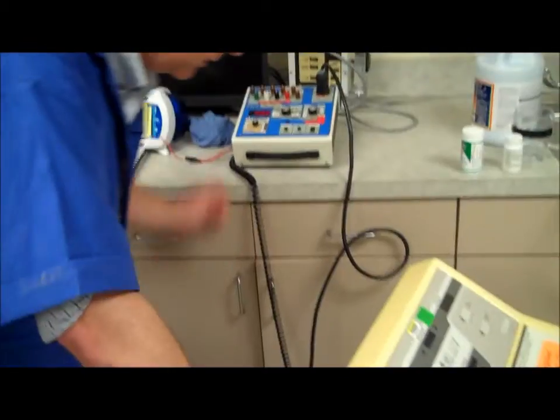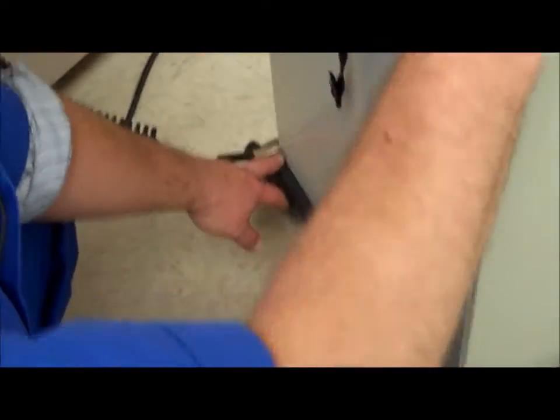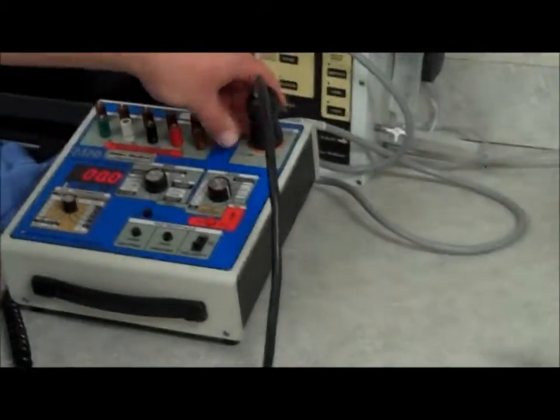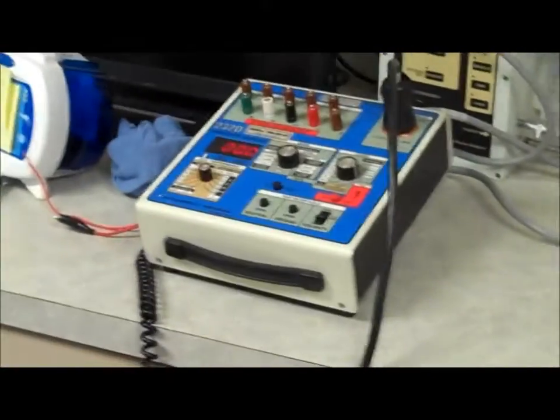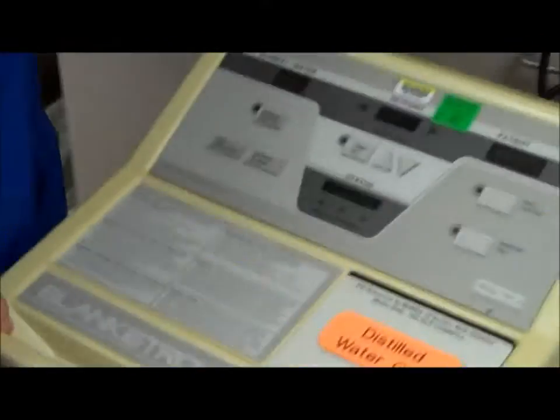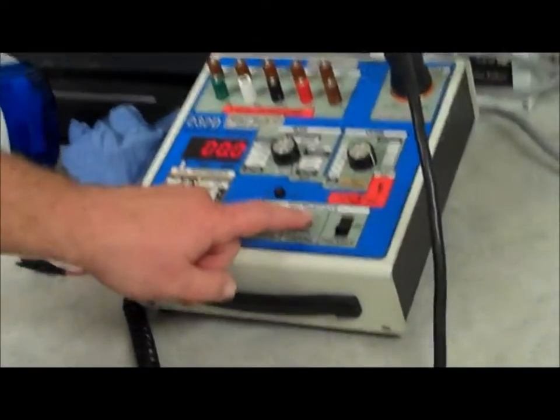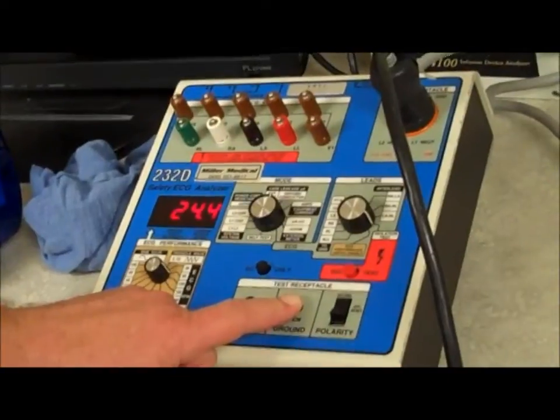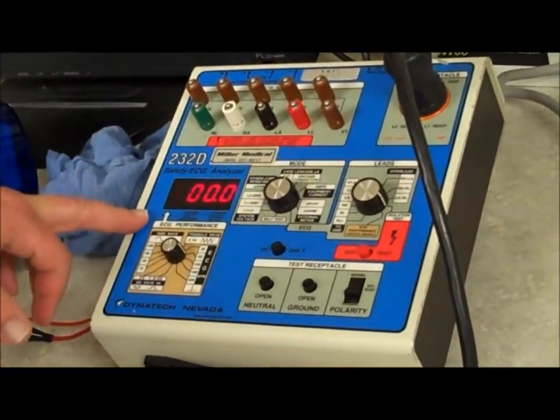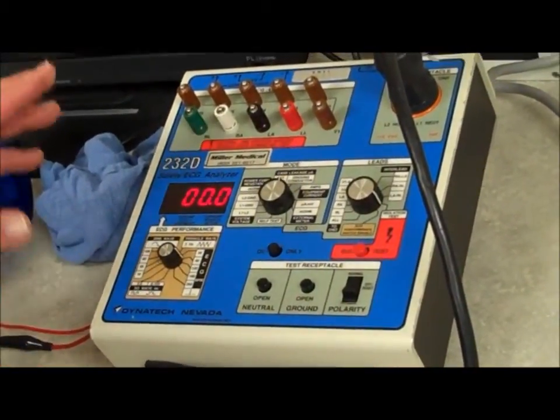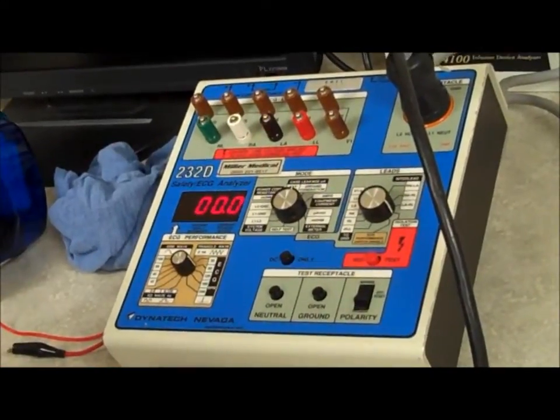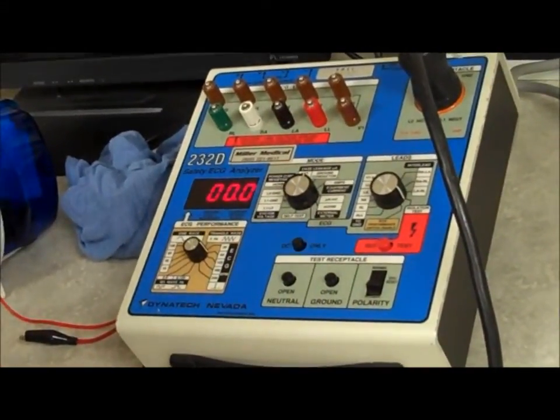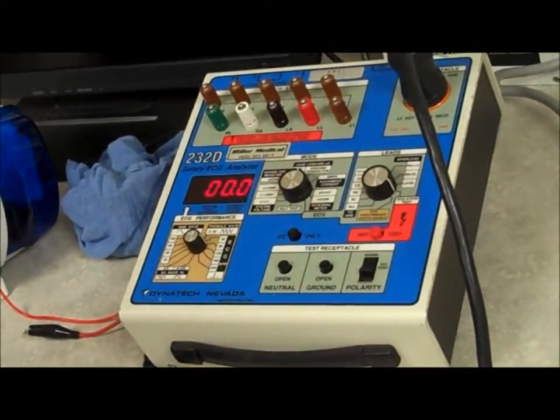Okay, now we're going to check the electrical safety on the Blanketroll 2. Have our analyzer. Hook our analyzer up to a ground point on the unit. The unit's going to be plugged into the analyzer, and we're ready to go. That's within our range. We want it to be below 100 microamps. Anything over 100 microamps, we might have a problem somewhere with this unit, and we have to figure out what we're up against.